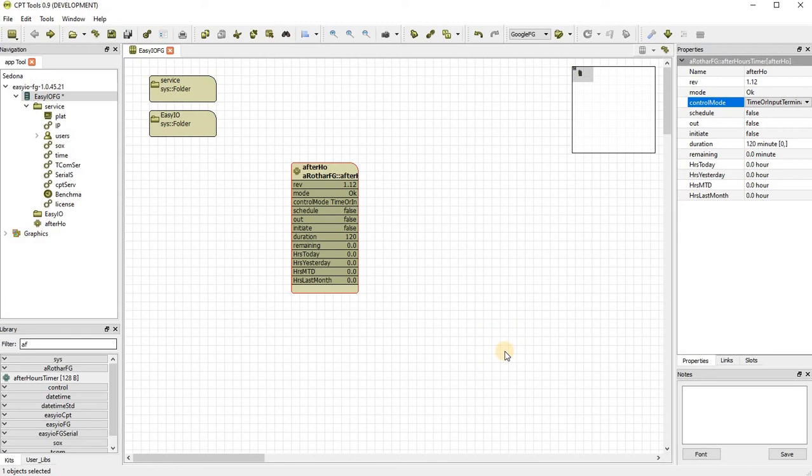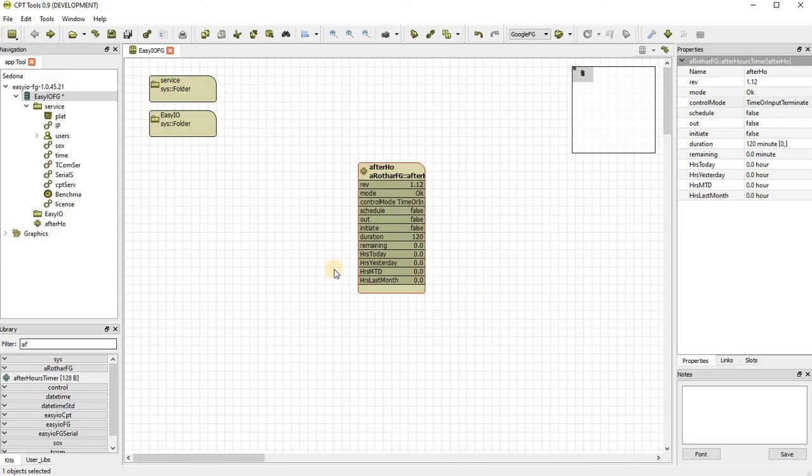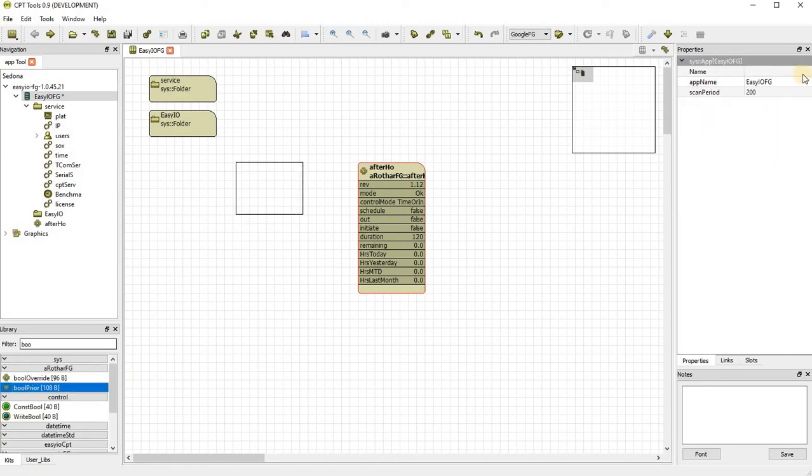So an example of this is someone comes in after hours, pushes their button, starts their system. The system runs for 15 minutes out of its 2 hours. Whilst going for coffee, they press the after hours timer again. This resets the timer for 2 hours. The tenant works for the full duration of the 2 hours and goes home. They'll be billed for 2 hours and 15 minutes. So it just resets the timer back to the duration of the time. The timer does not work when the schedule is on, so they can press the button as much as they like.